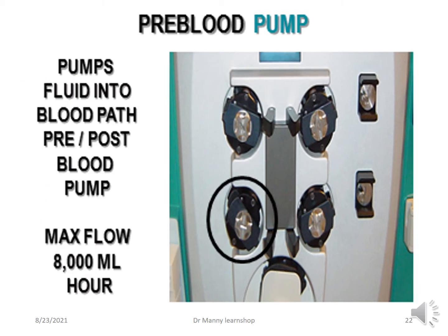The pre-blood pump pumps fluid into the blood path. This can either be done pre the filter or post the filter, and the maximum flow is approximately 8,000 mils per hour.